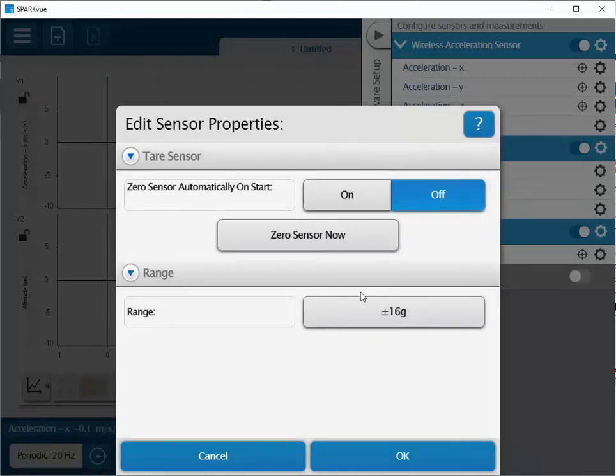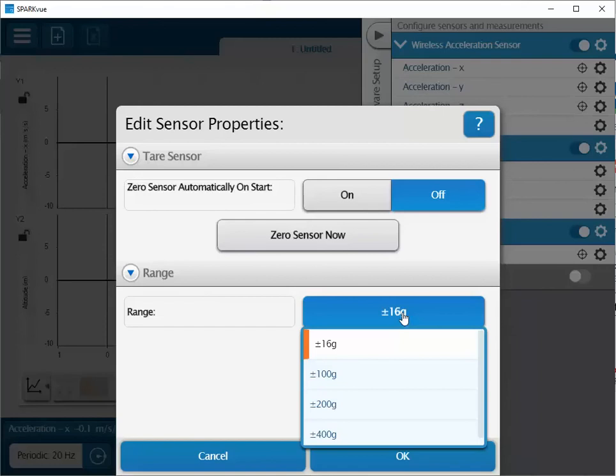Once there, select the range values from plus or minus 16 G's up to 400 times the acceleration due to gravity. Select the smallest range that encompasses all your data.